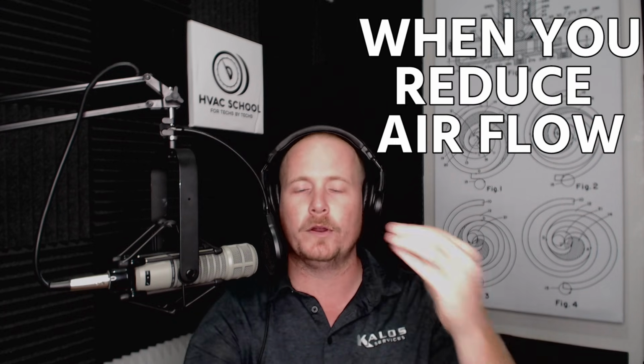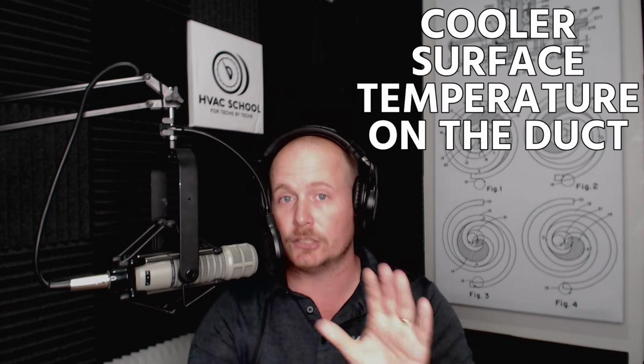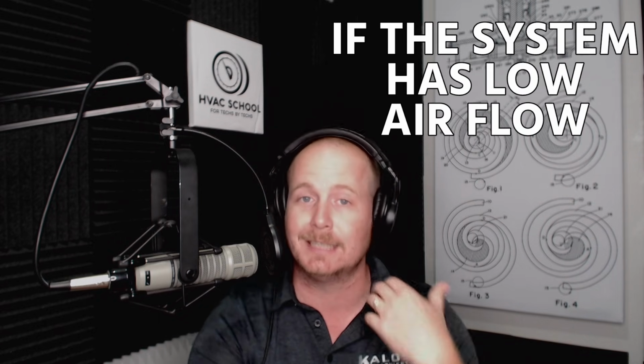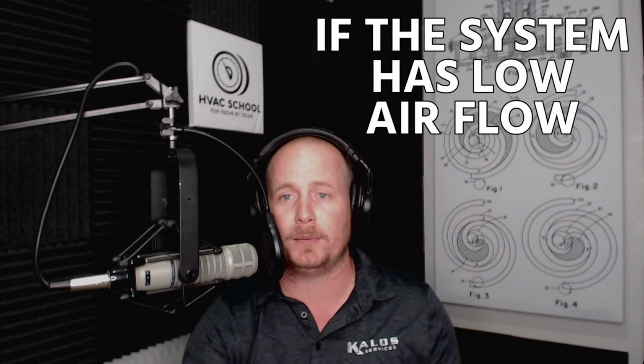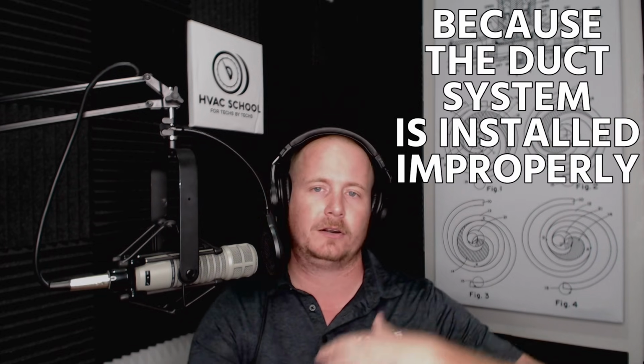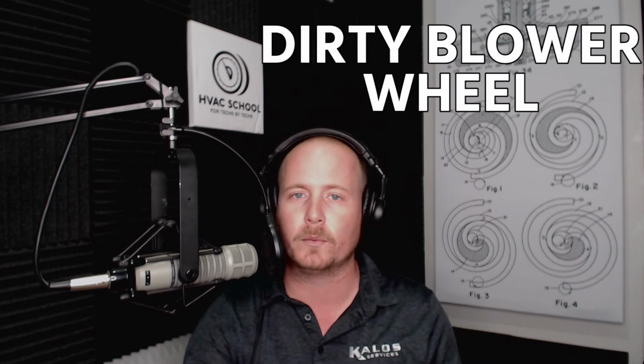But again, when you reduce airflow, that's going to create colder air inside the duct. You're going to have lower velocity through the duct, which is going to create cooler surface temperature on the duct. So if you have a situation where the system does have low airflow, this is the other side of this equation. If your system has low airflow because the duct system is installed improperly, or it has a dirty evaporator coil or a dirty blower wheel or something like that, then that can sometimes be a fairly easy fix.